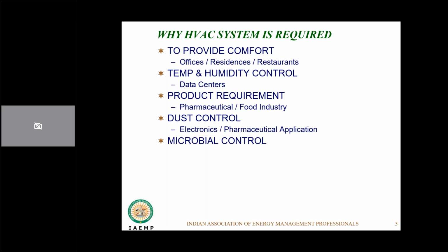When you're doing semiconductor industry, microbial control, again, pharma and hospitals are the two important areas. You don't want your system to become a cause of infection. Basically, in hospitals, in the current scenario, with the pandemic going on with COVID-19, hospitals sometimes become a major source of cross transmission of this virus, and HVAC plays a very important role in mitigating that risk, or if not done right, it can become a source of contamination. So we do a lot of evacuation strategies, and a lot of airflow patterns have to be designed when you're doing a containment ward, where you don't want the air which has been exhaled by an infected patient to go into the other zone. So microbial control comes into impact, which HVAC design has to take into account.